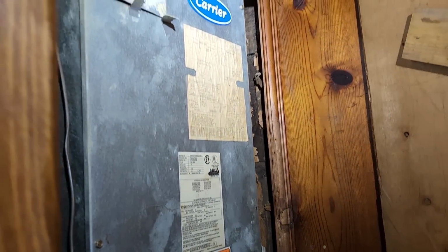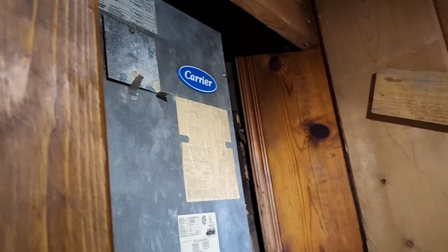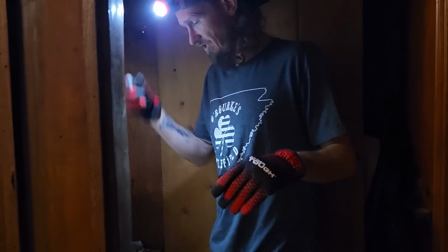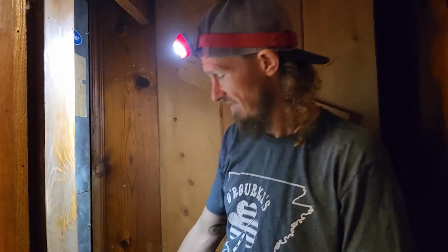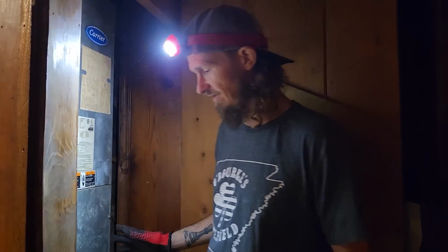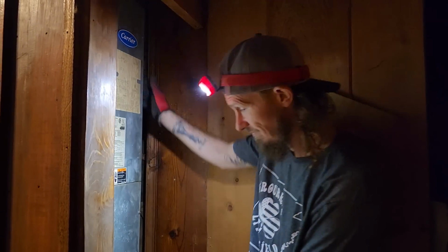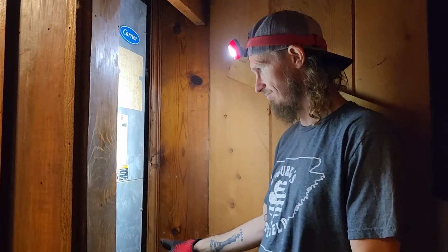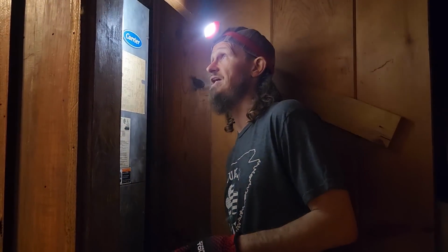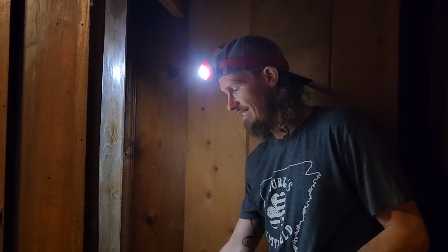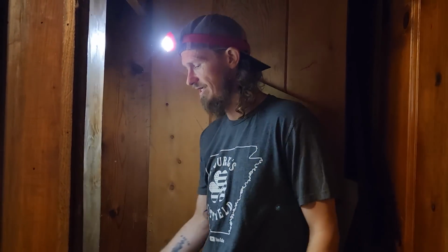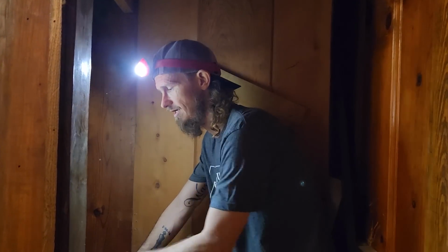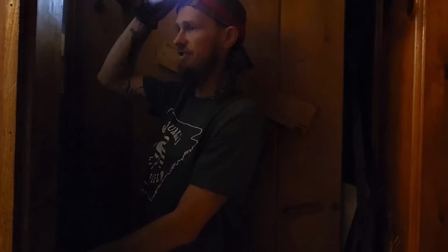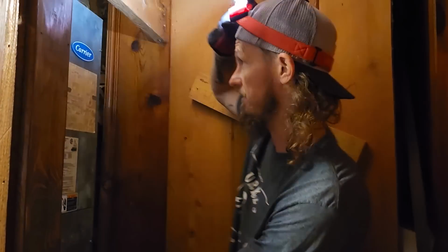Right now we got a really old carrier unit, we're going to take him out. The good news, in my opinion, is that it's wide open, so it should be very easy to work in here. And the plywood itself is still good on the bottom for the base, so I don't have to put a new base on it. I do have an SS2 safety switch that I'm going to put on it, and probably an SS1 in line, and that is just going to alert us if we get a backup in our drain line.